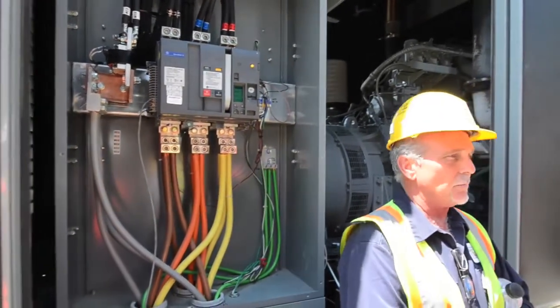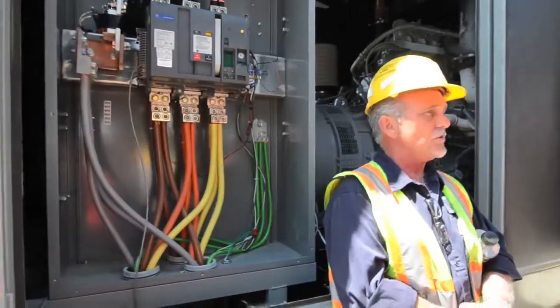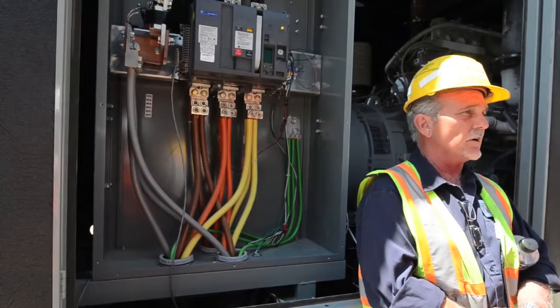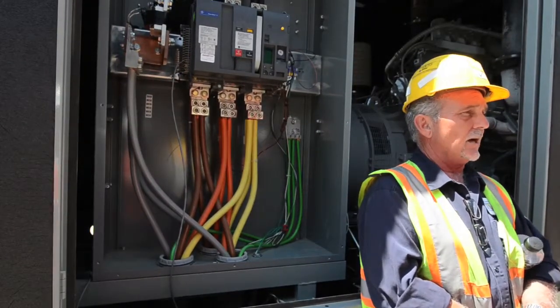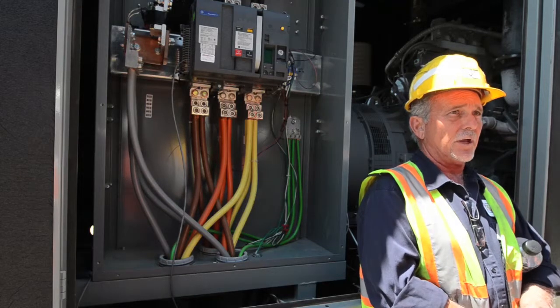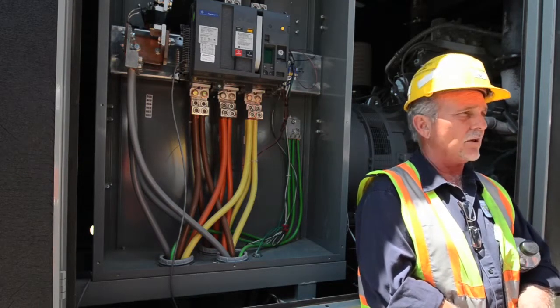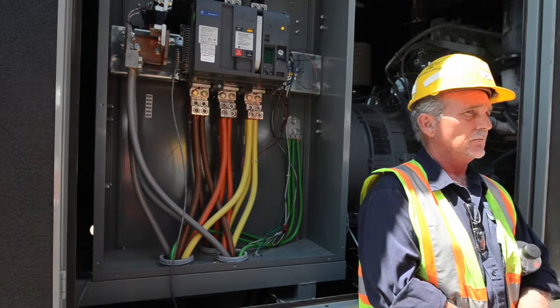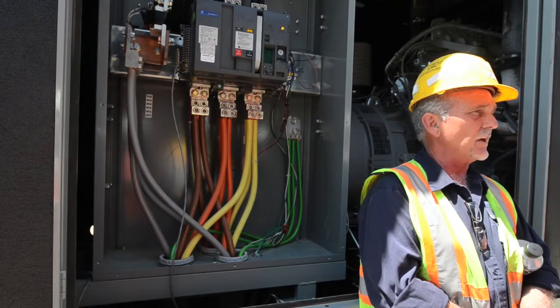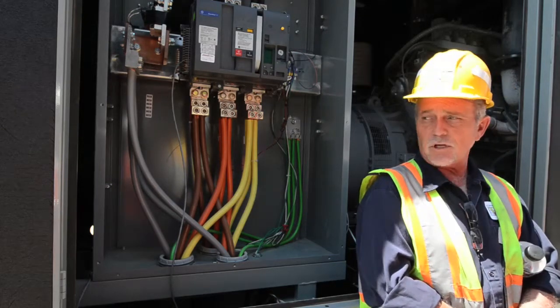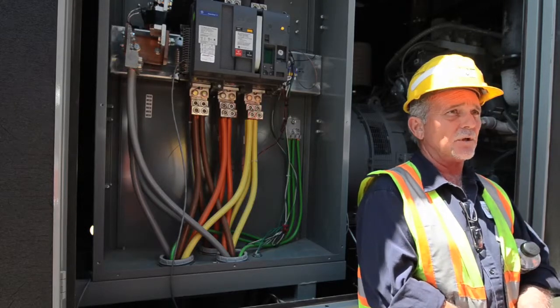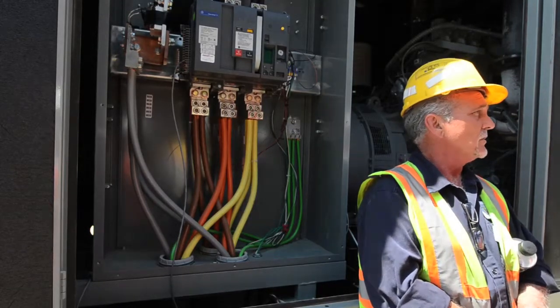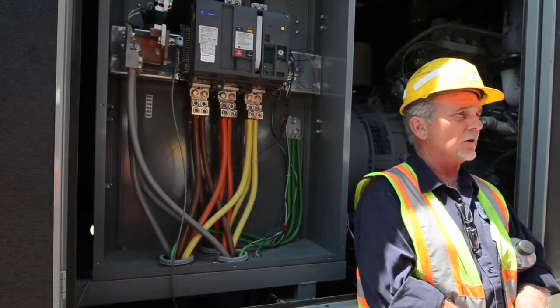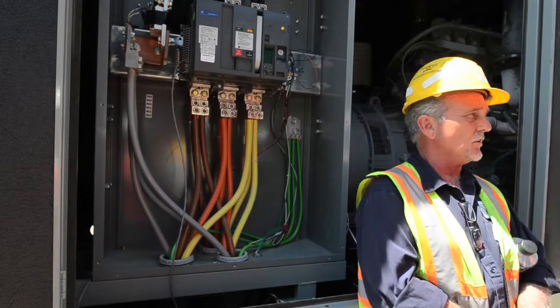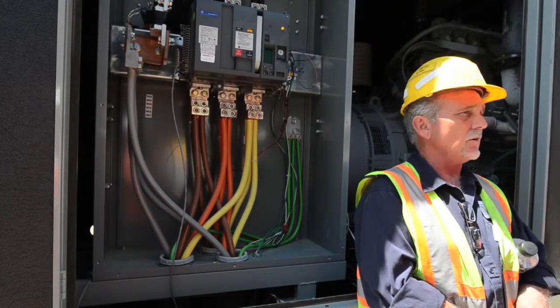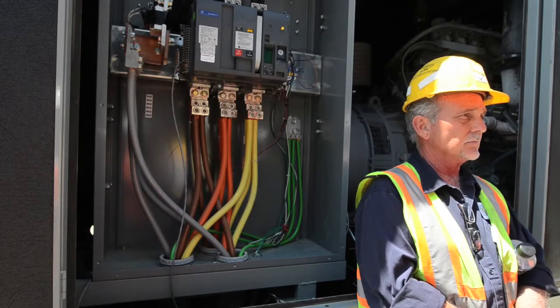I do that intentionally because I do not want one unit running and you reach over and try and close the breaker on two non-synchronized generators. Now, good part about that, it takes care of itself. The bad part is if there's a loss of communication or anything goes wrong, you can't force it closed. But that's a good thing in this application because this is what the company ordered, this is what they wanted, this is the application, this is how it works. And this is the protection systems that are involved in it. This is not unique to MTUs. It doesn't matter whose generator you buy, they're not going to give you control of that breaker.